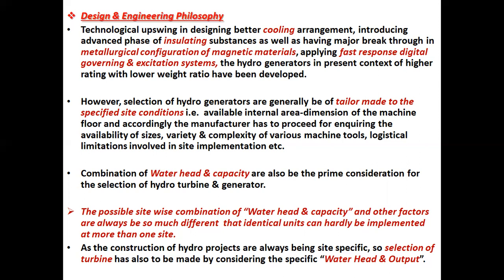I repeat, combination of water head and water capacity are also the prime consideration for the selection of hydro turbine and generator. The possible site-wise combination of water head and capacity and other factors are always so different that identical units can hardly be implemented at more than one site. It is an important phenomenon. That is the reason for which tailor-made generator and turbine is required.